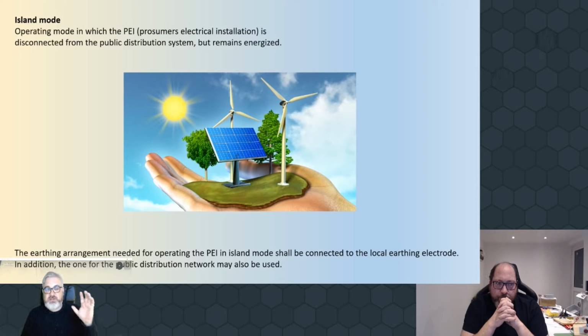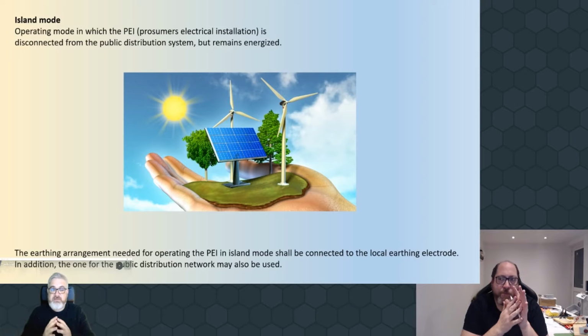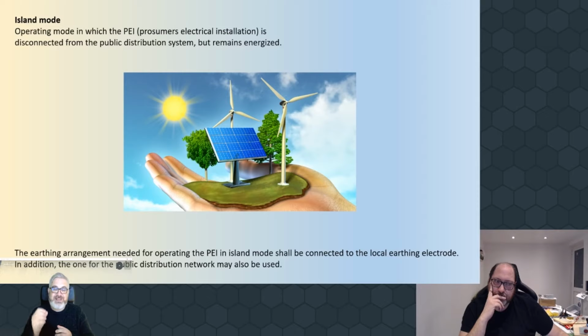So those watching this going, well, hang on a minute - if anybody remembers the DPC, there was reference to an additional earth electrode or a foundation earth electrode, which caused chaos, let's be honest about it, Dave. But it's in there, and I think this is why 60364-8-3 has come out for operations, because it says the earthing arrangement needed for operating the prosumer's electrical installation in island mode shall be connected to the local earthing electrode.